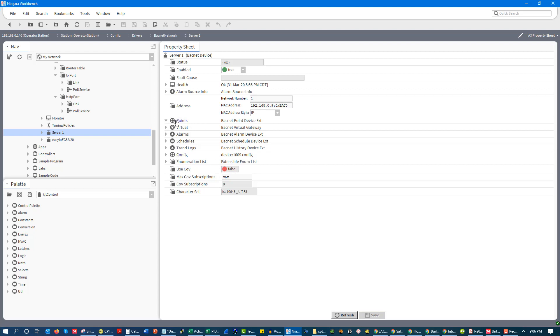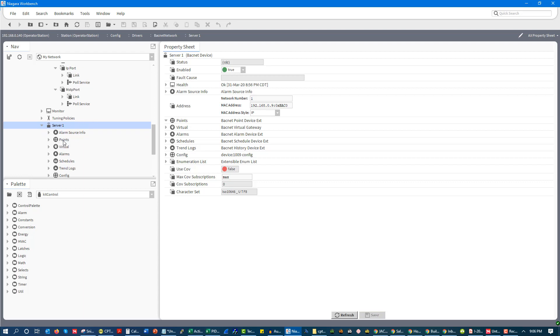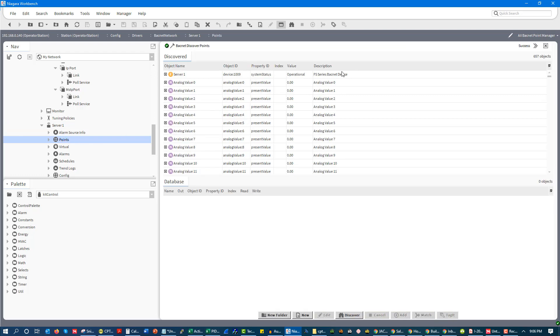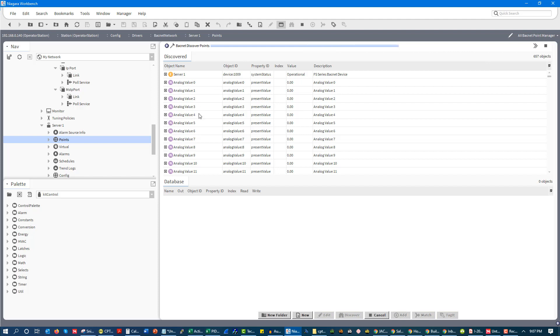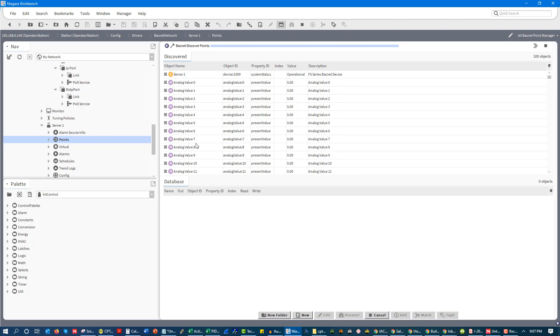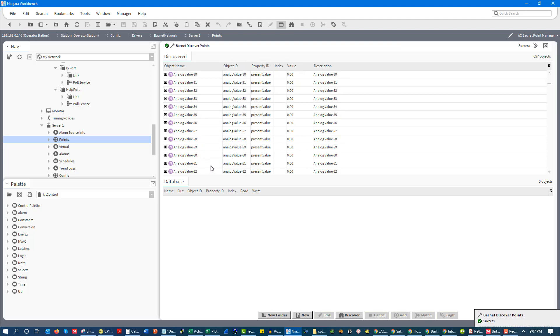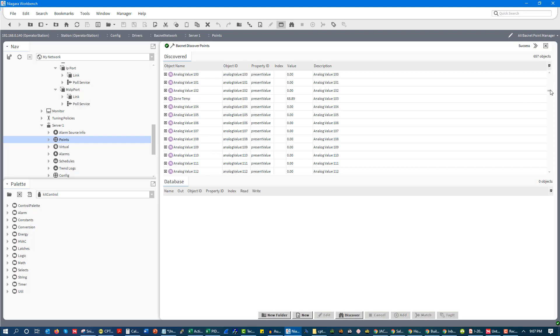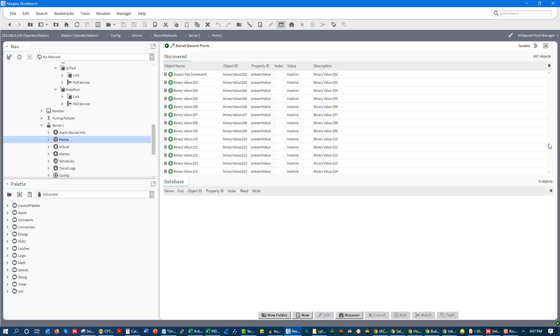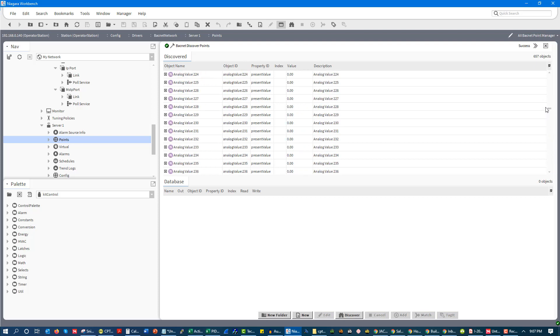Now, obviously, it's all well and good that we have our controller mapped in, but you probably want to get the points from the controller mapped in, too. So this is where we go, and we do discovery of our points. So if I run our discovery, and we're going to see it's running up here, and it's going to pull every point that is available within the controller. And a lot of these points I left named analog value. And the reason why is I want to show you the importance of properly naming your points.